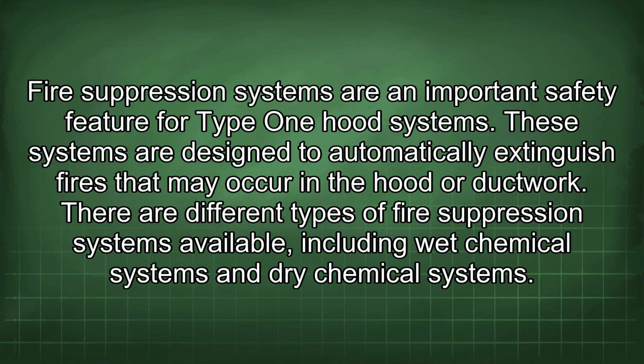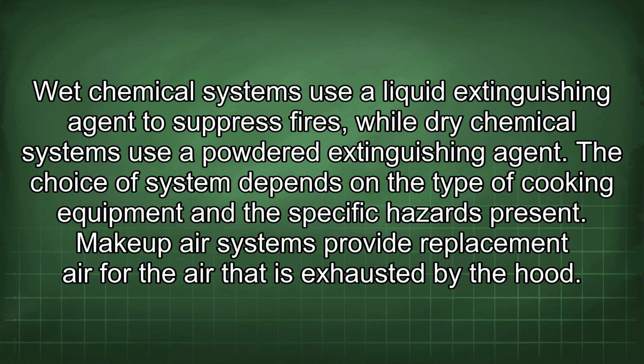Fire suppression systems are an important safety feature for Type 1 hood systems. These systems are designed to automatically extinguish fires that may occur in the hood or ductwork. There are different types of fire suppression systems available, including wet chemical systems and dry chemical systems. Wet chemical systems use a liquid extinguishing agent to suppress fires, while dry chemical systems use a powdered extinguishing agent. The choice of system depends on the type of cooking equipment and the specific hazards present.